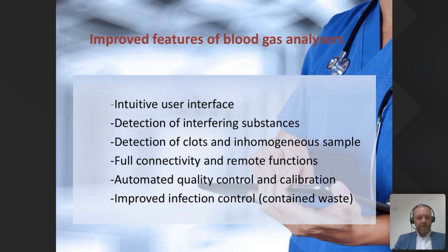One of the vast improvements over probably the last 5 to 10 years has been detection of interfering substances. Benzalkonium is one of those, but there are a number of others that can give you error patterns on the blood gas analyzer, which you can then choose to either not accept the results and have those held back on the analyzer, or to present them with a warning to the clinician to take a little bit of caution in interpretation. We're all very used to detection of clots on these solutions, and the detection of inhomogeneous samples.